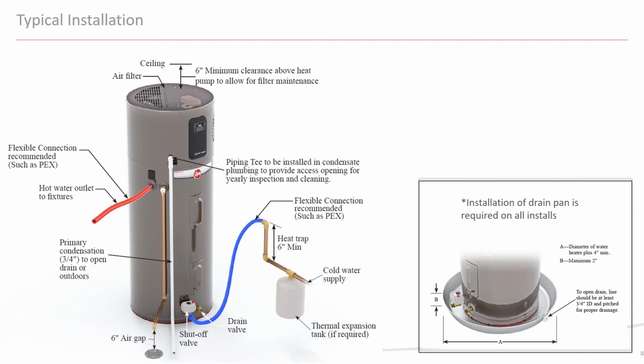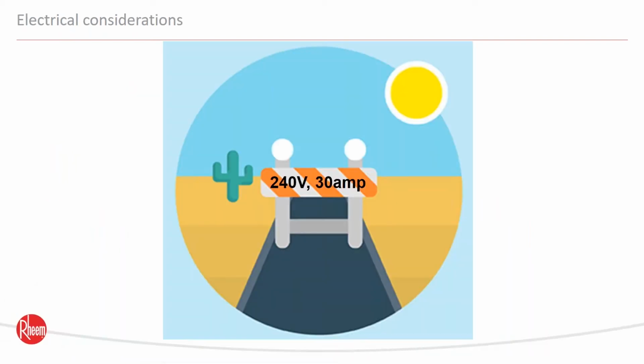Other considerations are going to be the air exchange. So all manufacturers require 700 cubic feet of space in order to exchange out heat. That's a 7 by 10 by 10 room. If you're in a garage, you're golden. If you are in a smaller closet, then you have to either put a louvered door in, that way it can breathe into the hallway, or you can duct them. And every single manufacturer will have ducting kits and allowances listed in their use and care manual.